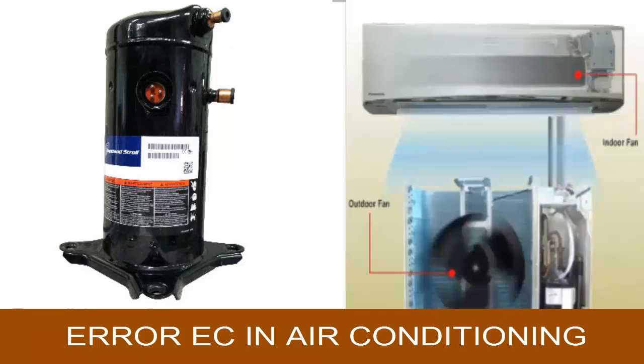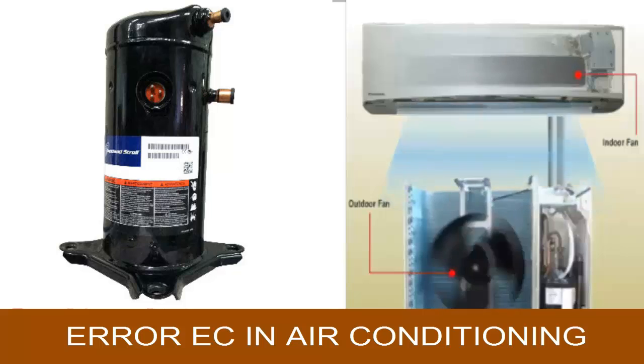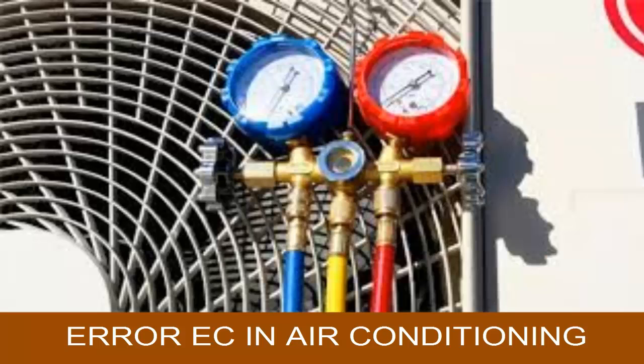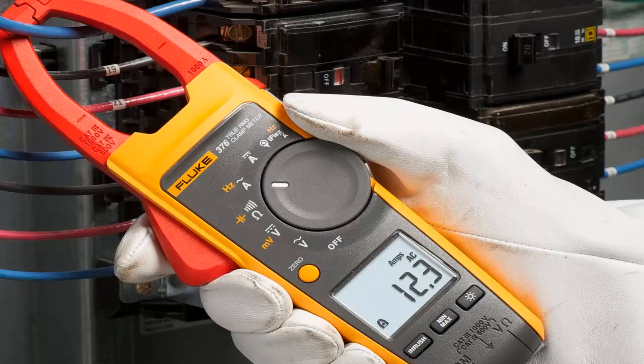If the compressor is running, check the refrigerant level using a manifold gauge. Perform these checks quickly to prevent the system from generating an error again. You can also use an amperage clamp to measure if the current consumption is normal, which helps rule out refrigerant leaks.